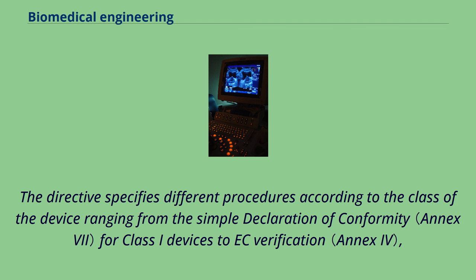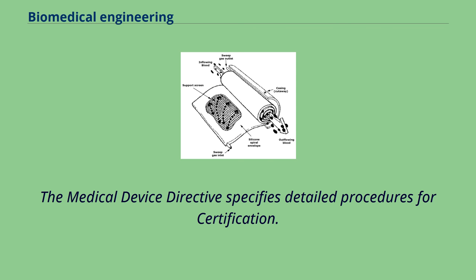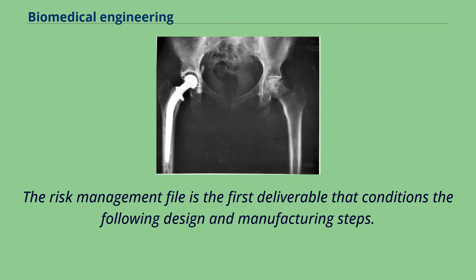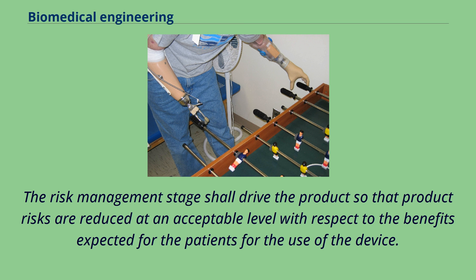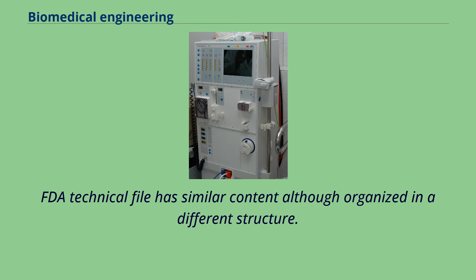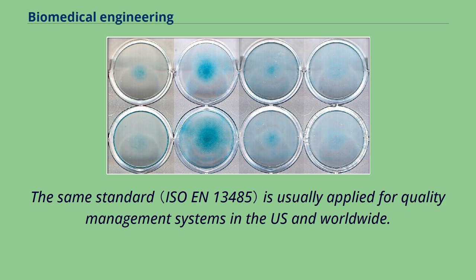The directive specifies different procedures according to the class of the device, ranging from the simple declaration of conformity for class I devices to EC verification, production quality assurance, product quality assurance, and full quality assurance. The Medical Device Directive specifies detailed procedures for certification, including tests and verifications contained in specific deliverables such as the risk management file, the technical file, and the quality system deliverables. The risk management stage shall drive the product so that product risks are reduced at an acceptable level with respect to the benefits expected for patients. The FDA technical file has similar content although organized in a different structure.